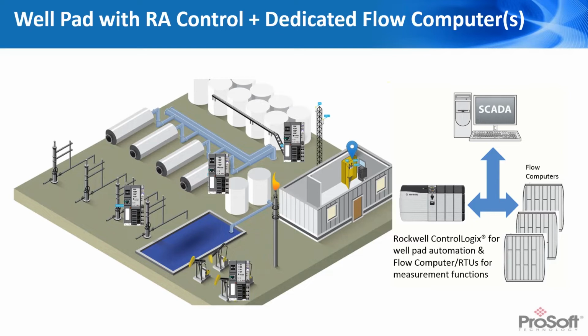In this drawing, I show distributed IO being used to take advantage of placing wiring directly next to separators and tank batteries at the wellhead itself, and then you've got your control system there. This is a big benefit when you're commissioning and setting up the system - it allows you to reduce your overall cabling runs all the way back to a control room or control panel. At that point, you're just essentially providing Ethernet and power right at the location you need.